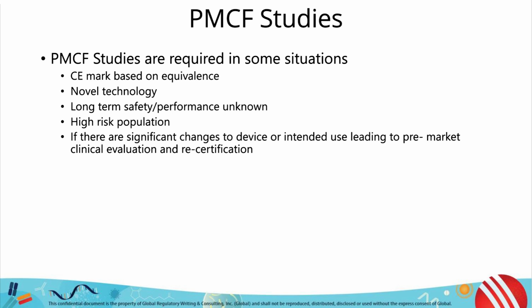In certain cases, a PMCF study might be required. This could include situations in which a CE mark was granted based on claiming equivalence to another device, if a device constitutes a novel technology, if the long-term safety or performance of the device is unknown, if the device is intended to be used in a high-risk population, and if there are significant changes to the device or its intended use.